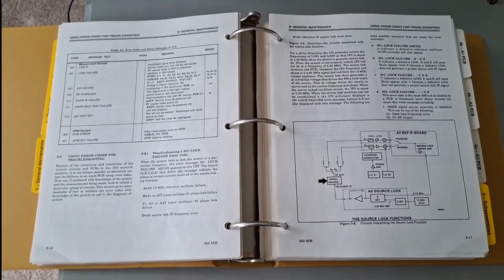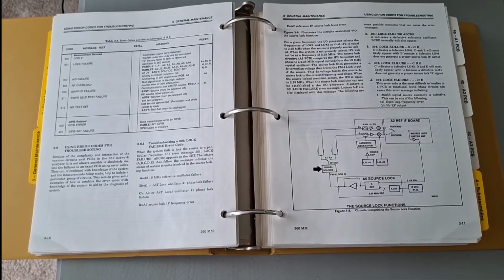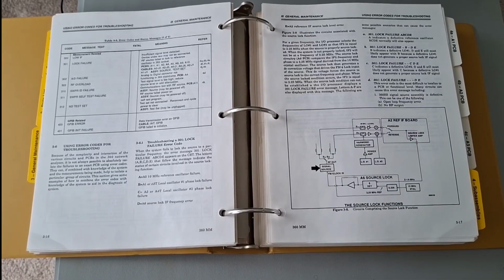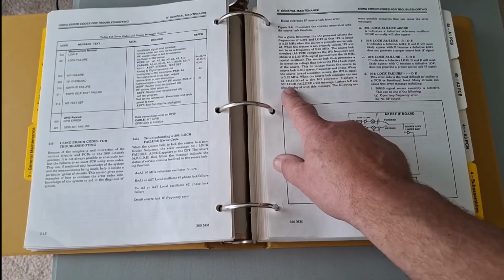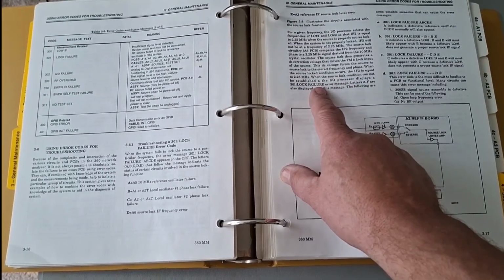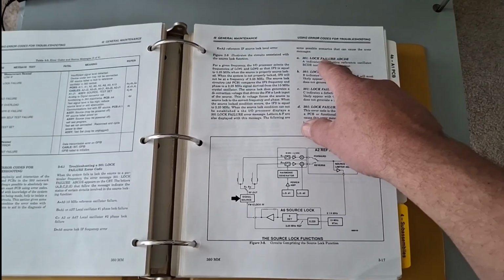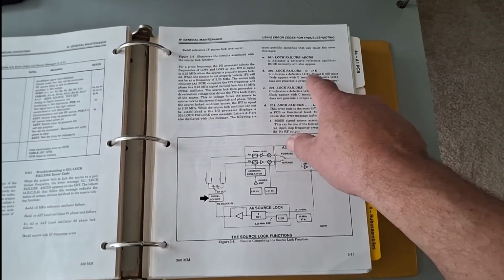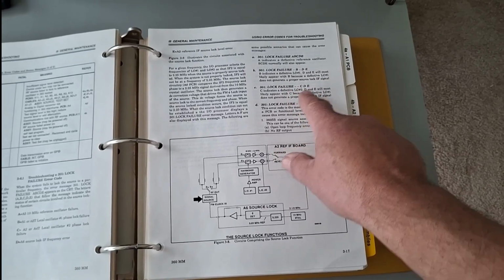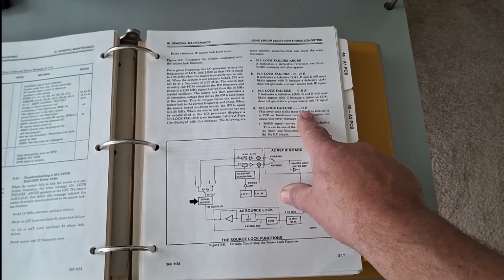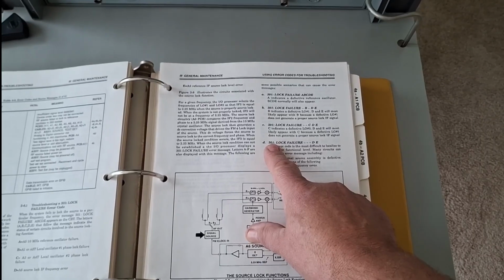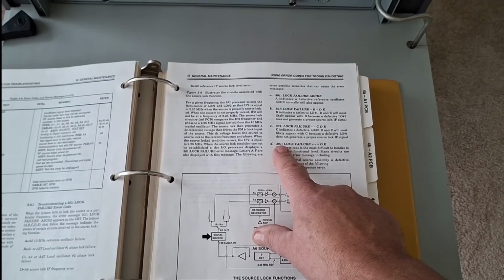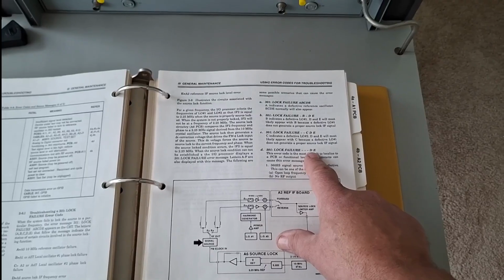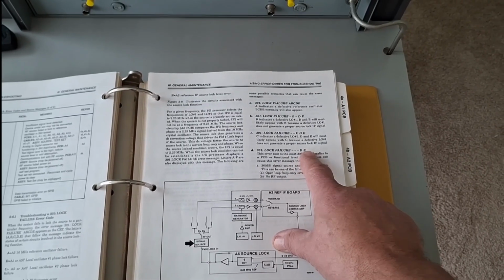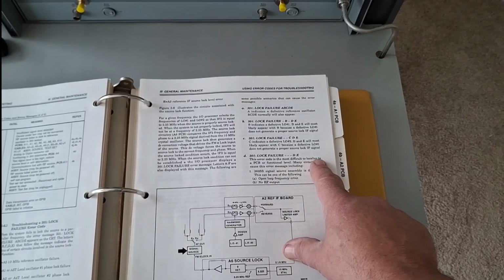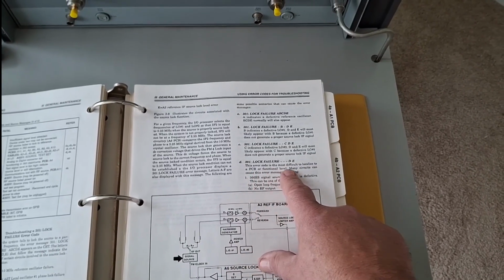Most importantly for me, the error codes and the fault finding information includes specific information on lock failure. And not only does the lock failure message indicate that there is a lock failure, there are letters after the lock failure message, in my case DE, and for this error code, the manual says that for lock failure 301 DE, which is the message that I have seen, this error code is the most difficult to localize to a PCB or a functional level.